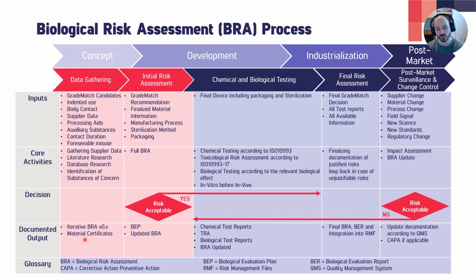Good. So how do you document this? You make a biological risk assessment for each and every iteration. So you start, you do a biological risk assessment, you gather data, then you have your iteration. If you're not happy with it, you reiterate, and all of the data that you gather during this iteration will find its place in the next iteration of your biological risk assessment. For those of you who are a little more advanced in biological risk assessment, it's the same approach that you will be using for a post-market phase or a change control phase. It's called the Lifecycle approach.